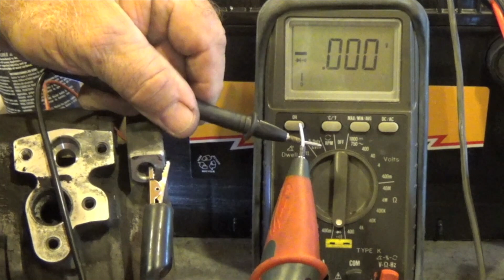Now, a continuity test does not tell you a circuit is good, it just tells you you do not have an open. If there's continuity, that means whatever's coming to that wire goes through that wire. It doesn't tell you how good it is, because we would have to load test it to find that. But it tells us, when I hear the beep, that these two wires are touching. So if I touch this block, which I've supplied ground to, and I touch this bolt, you can see that we have 0 volts, so we're on the ground side, and you can hear the beep.